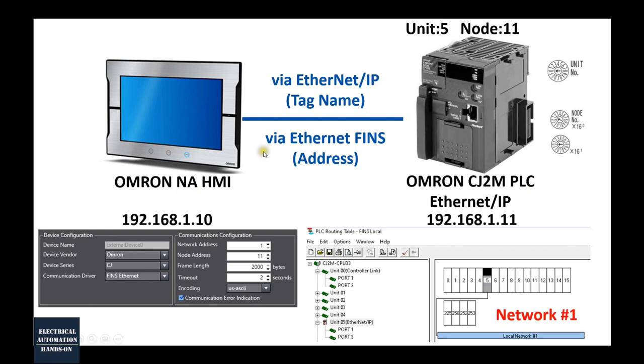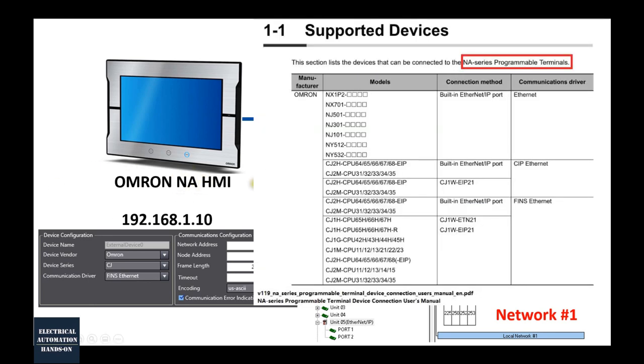So why are we going to use the NA HMI with a CJ2M PLC? This is a retrofit project with an existing CJ1M PLC, which is an older style and doesn't have built-in EtherNet/IP. So in this project, we upgraded the CJ1M to CJ2M, which has built-in EtherNet/IP. That allows us to connect to I/O banks, robots, or other HMIs using an Ethernet cable. I also confirmed that the NA series HMI definitely supports the CJ2M PLC.